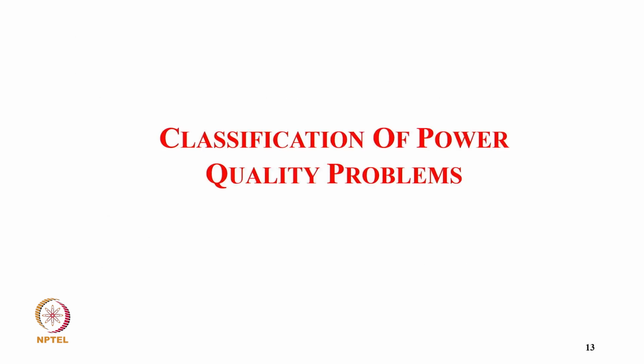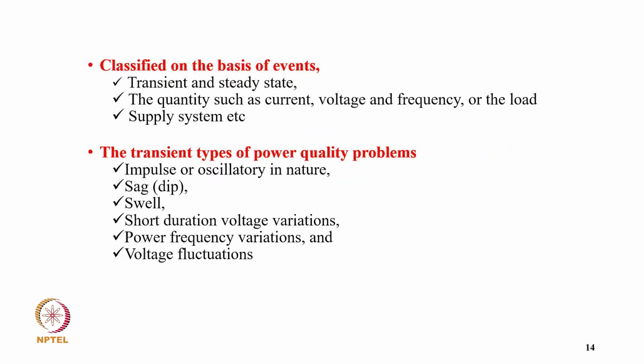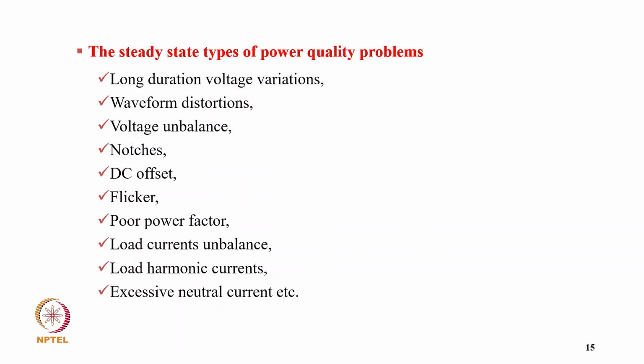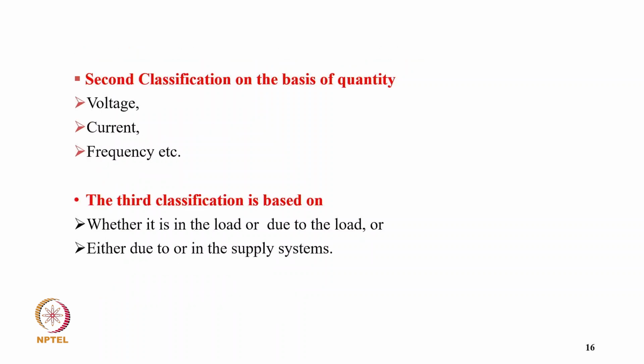Now coming to the classification of power quality problems. Classification is on the basis of event, transient and steady state, the quantity such as current, voltage and frequency, or load and supply system, etc. Transient type power quality problems are impulse or oscillating nature, sag, swell, short duration voltage variation, power frequency variation, voltage fluctuation. And steady type power quality problems are long duration voltage variation, waveform distortion, voltage unbalance, notches, DC offset, flicker, poor power factor, load current unbalance, load harmonics current, and excessive neutral current, etc.